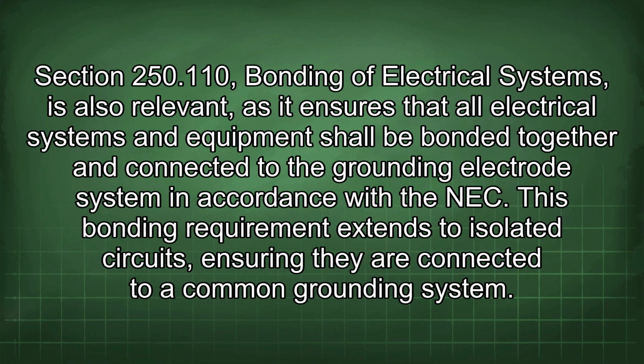Section 250.110, Bonding of electrical systems, is also relevant, as it ensures that all electrical systems and equipment shall be bonded together and connected to the grounding electrode system in accordance with the NEC. This bonding requirement extends to isolated circuits, ensuring they are connected to a common grounding system.